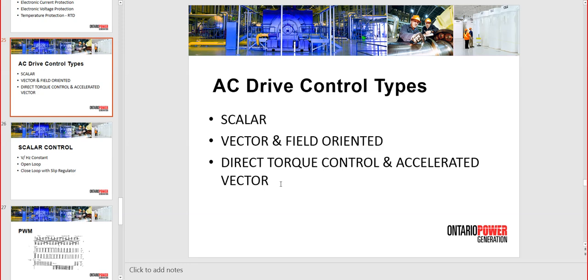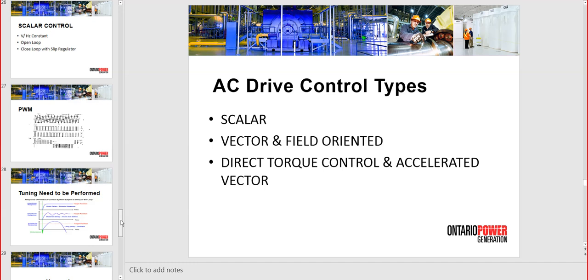Now direct torque control you don't really need if you don't foresee a torque control application. What is a torque control application? I may want to control the torque on a certain material that you pull with the shaft, so you don't want to break paper or rubber or whatever, so I want to keep a constant torque at the shaft, and that's where the torque control kicks in.